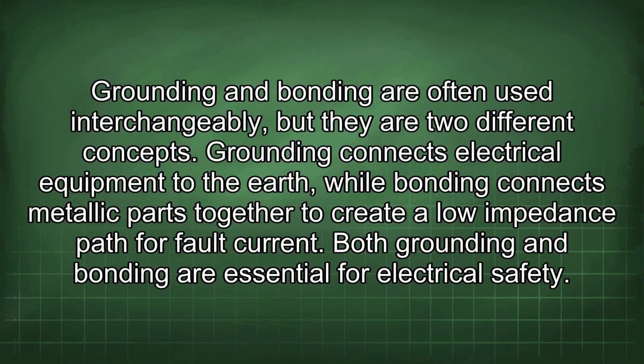Grounding and bonding are often used interchangeably, but they are two different concepts. Grounding connects electrical equipment to the earth, while bonding connects metallic parts together to create a low impedance path for fault current. Both are essential for electrical safety.